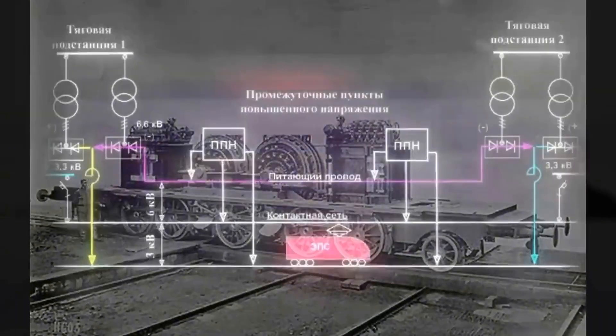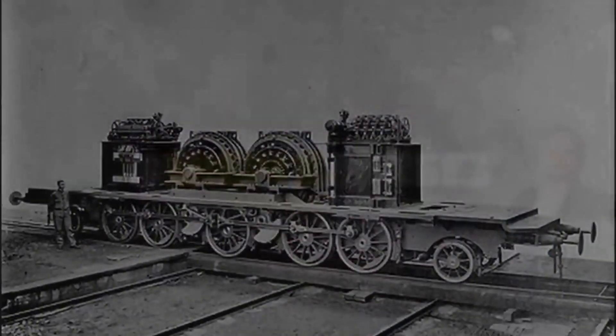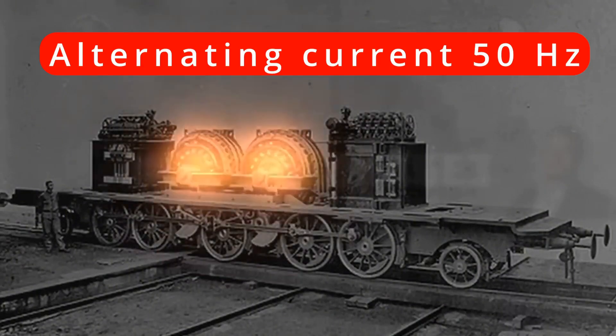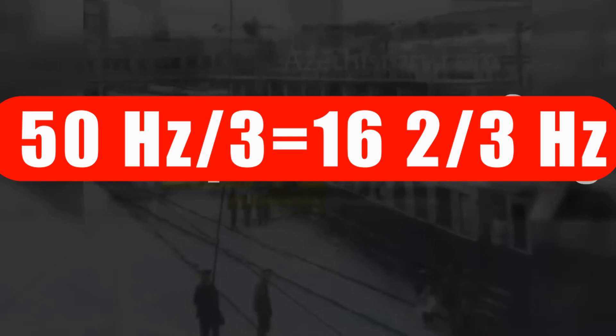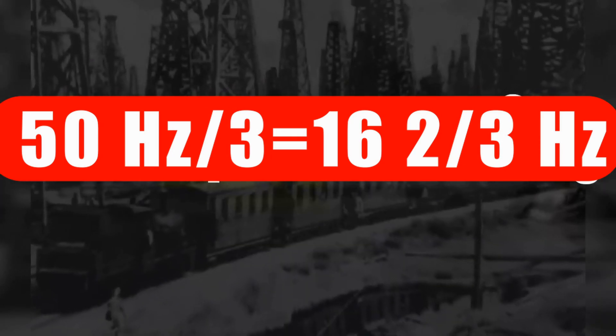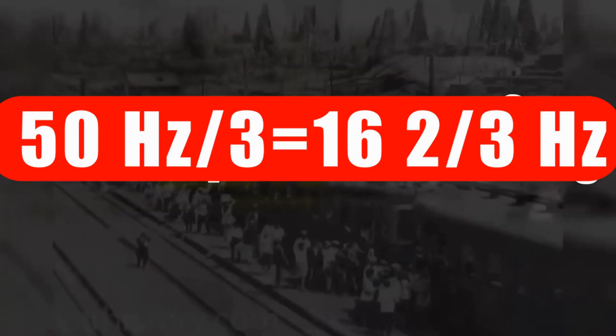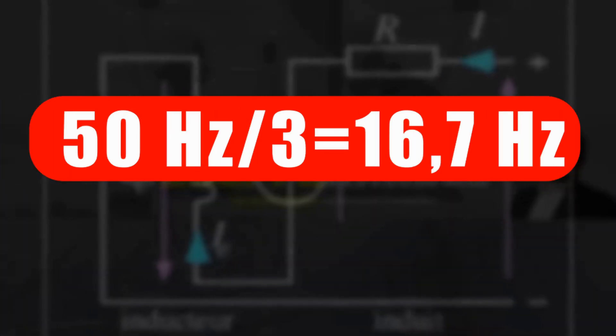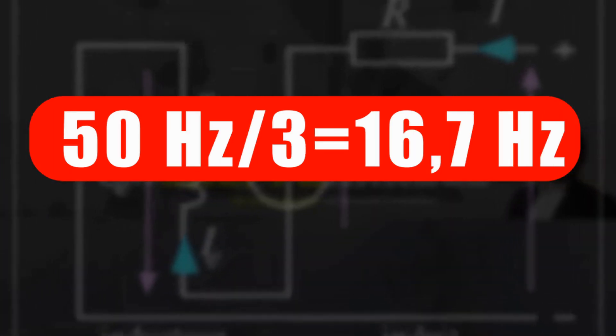They wanted to use the same series wound DC motors for alternating current, but at 50 Hz these motors would experience excessive heating and losses. So they came up with nothing less than reducing the frequency by a factor of 3. If you divide 50 by 3, you get 16.67, but then they rounded it a bit to 16.7 Hz.